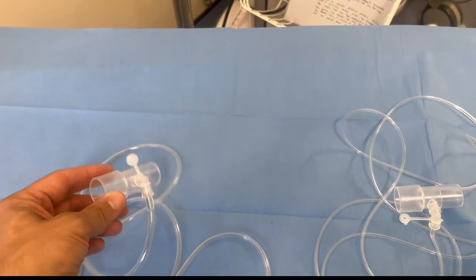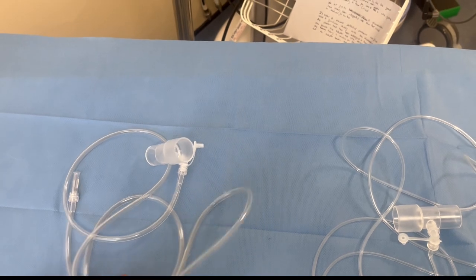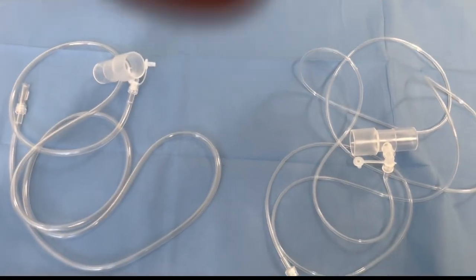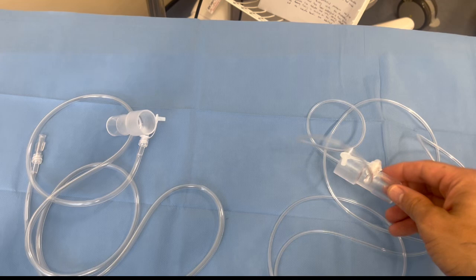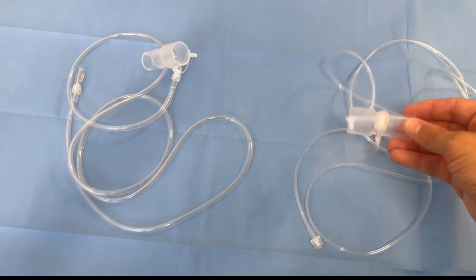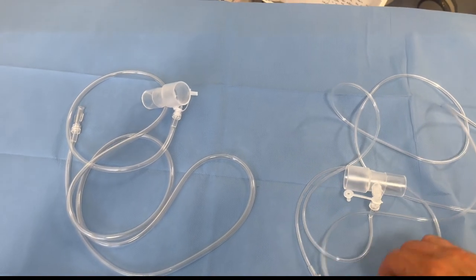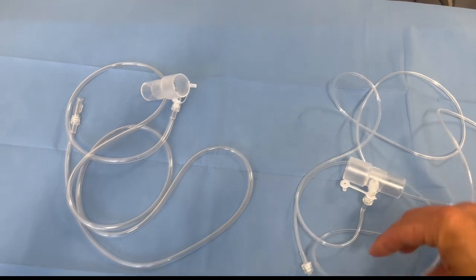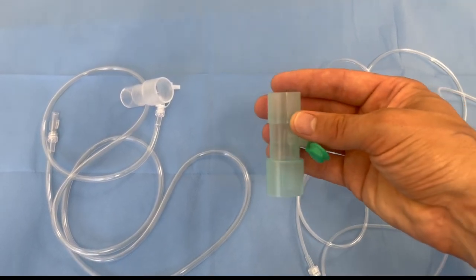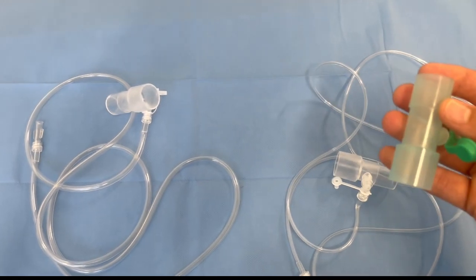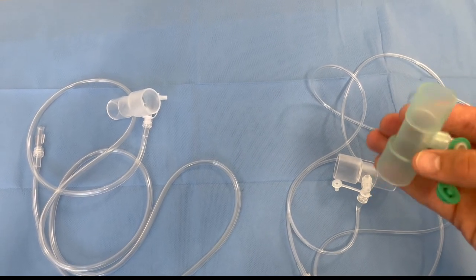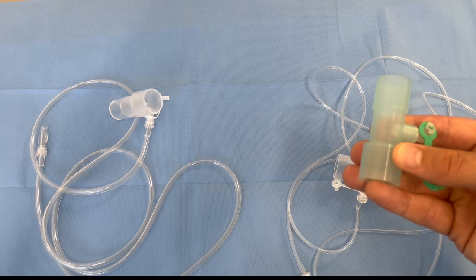Here we can see the nitric injection adapter. The tubing is a little bit thicker. Here we can see the sample line adapter. The tubing's a little bit thinner. You can see how they could easily be mixed up, and to avoid this we've procured another adapter to be used on the sample line, so it's less likely that mistakes will occur.